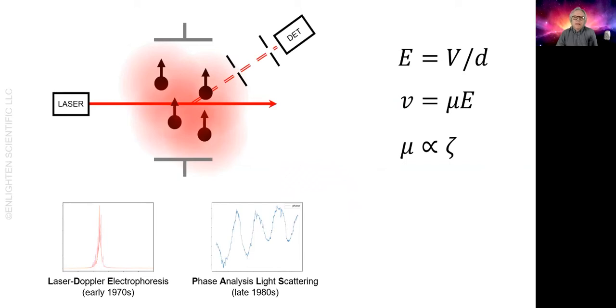Instead, you get a single average value. Above 10 millimolar ionic strength, commercial instruments switch to using PALS simply because they cannot do the laser Doppler measurements. But PALS measurements are only valid if the sample is truly monomodal with respect to zeta potential. You have to assess whether that's an appropriate assumption for your particular purpose.